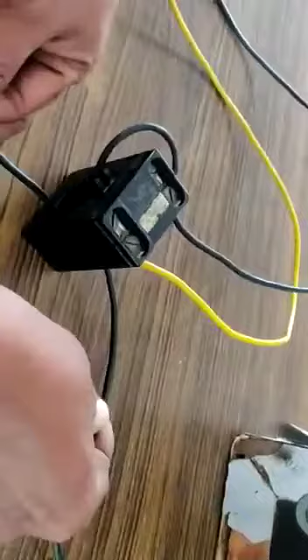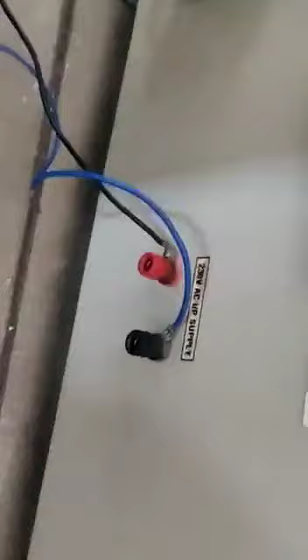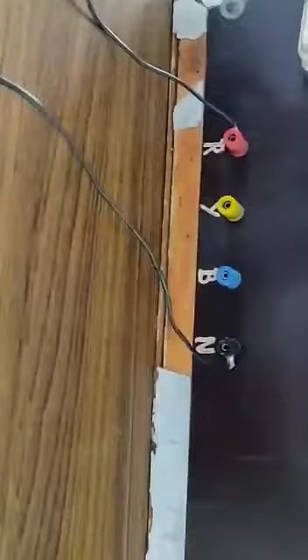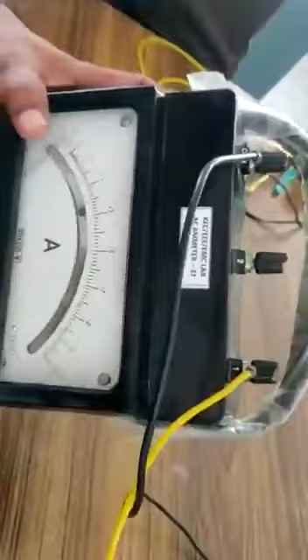This is primary winding of CT. One end connected to supply, other end connected to ammeter one end. Ammeter is 0 to 15 amps. The other end of ammeter connected to load point, blue wire. Whereas the load point other terminal should be connected to neutral of supply, the black wire. Where the secondary of CT is connected with low range ammeter 0 to 1 amps. This is how you have to connect for calibration of CT.